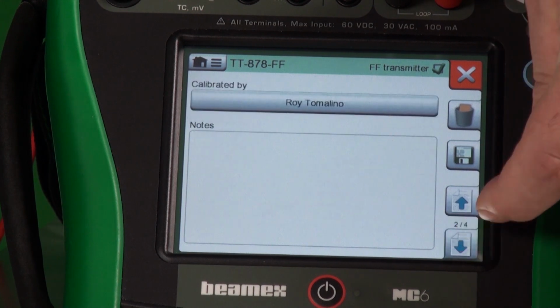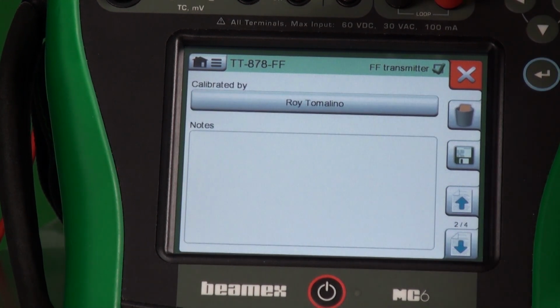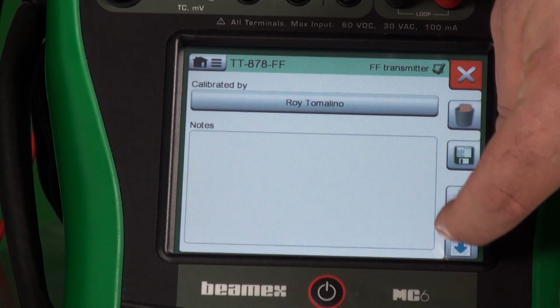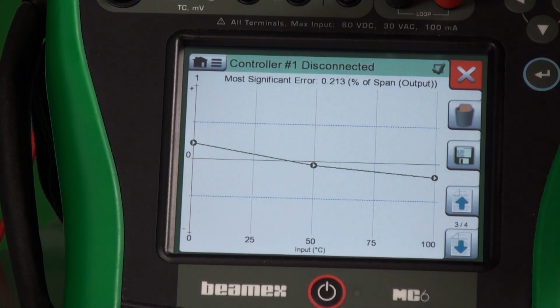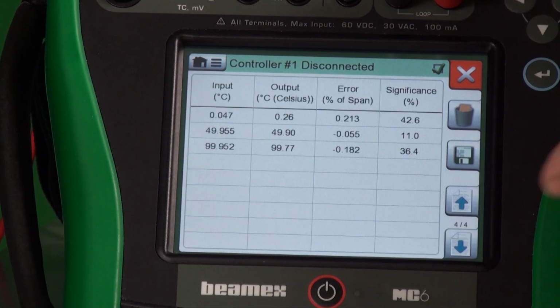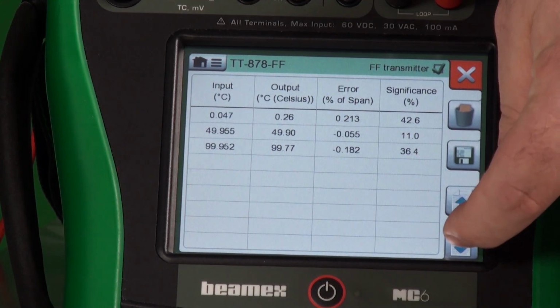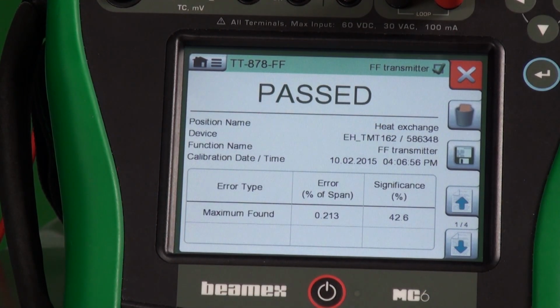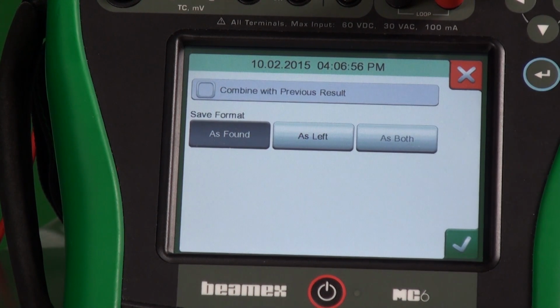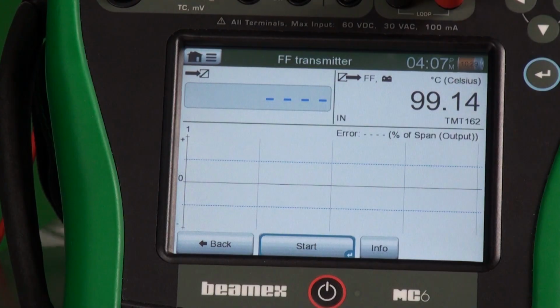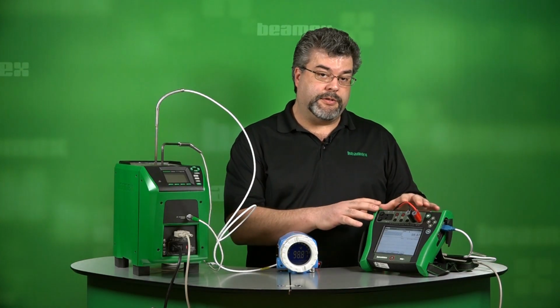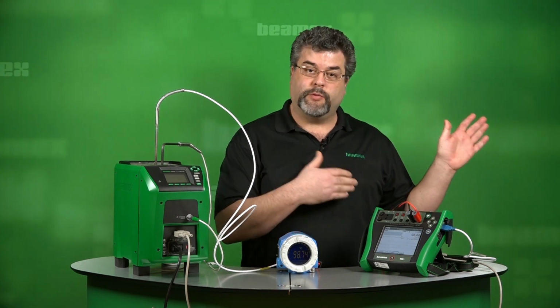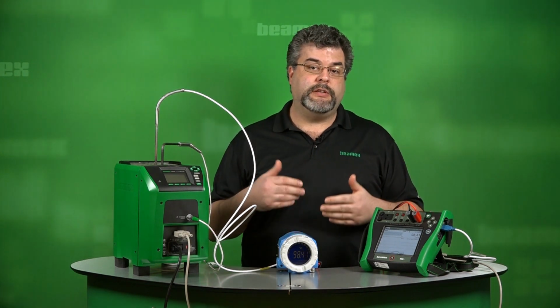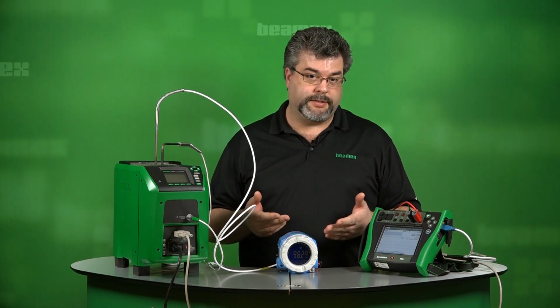We can cycle through the screens and we can put in extra notes if we need to that pertain to the calibration record. And we can see what our graph looks like as well as the raw data. If we hit down again, it simply cycles back around. But let's save this test. And this was an as found test and it did pass, so let's go ahead and hit the check mark. At this point, our data is saved. We could power this down and take it back to the instrument shop if we needed to, or maybe head over to the next device that we needed to test.